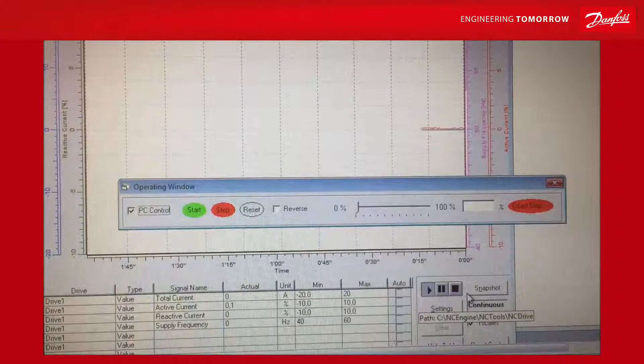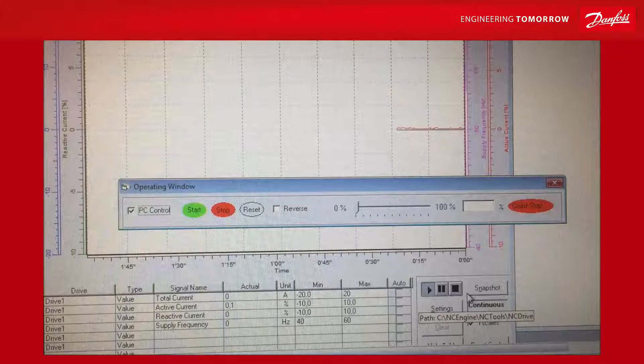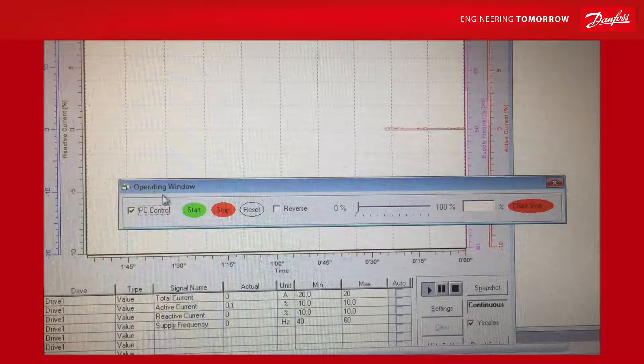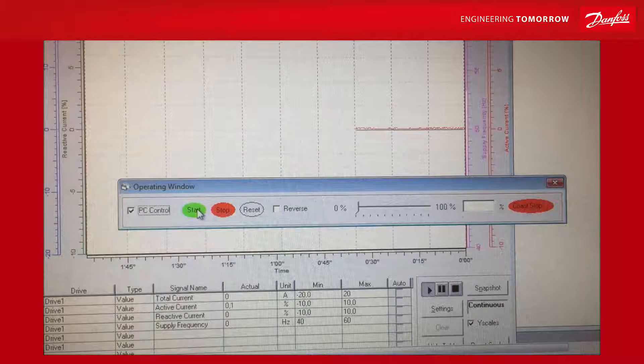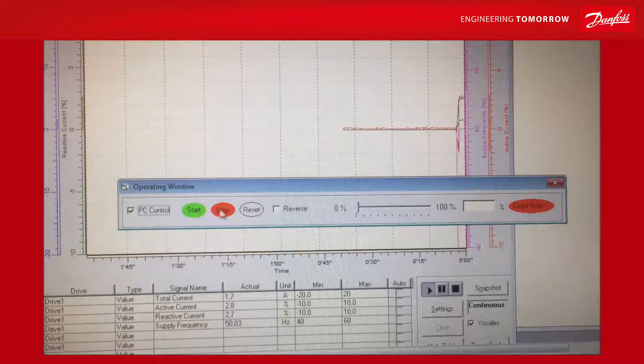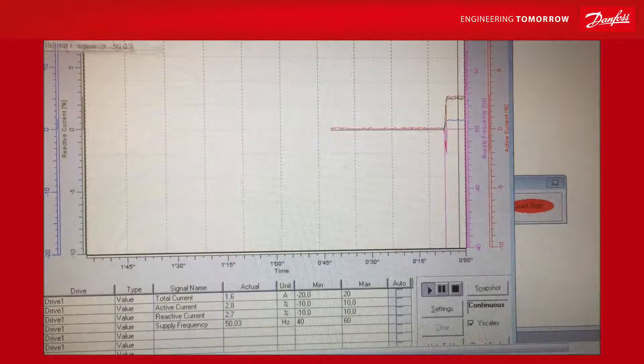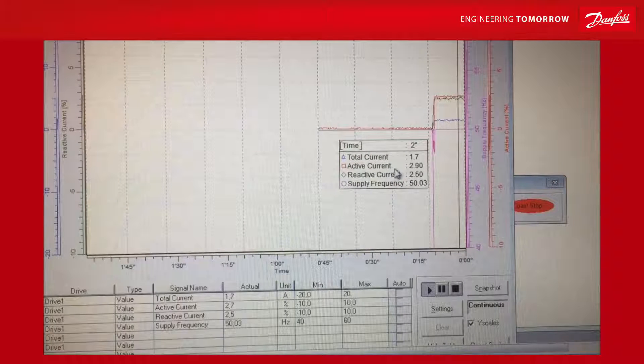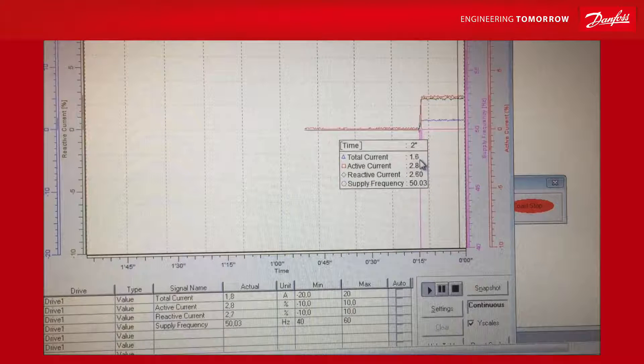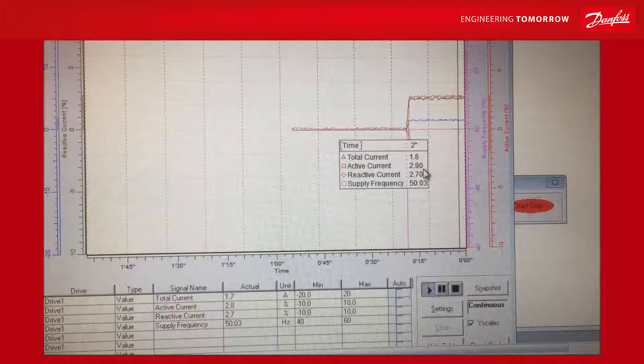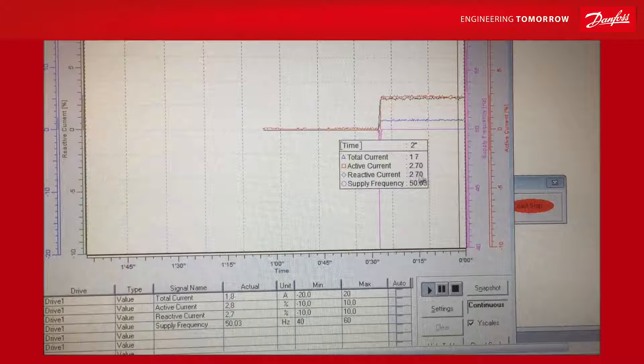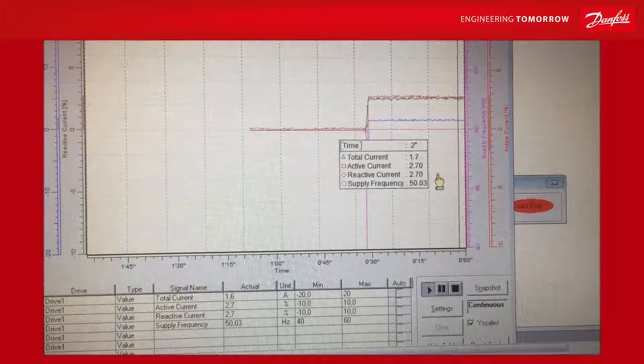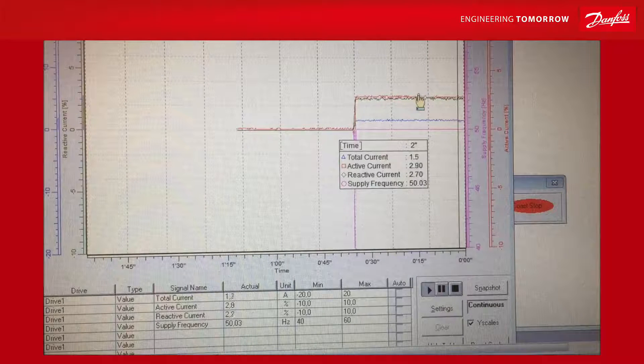With only those few basic parameters in, let's try to start it, just like it was a shore power. It is not synchronizing to any grid yet — it is just making its own grid. We have selected the operating window, PC control, so my laptop is now start/stop of this system. I can reset any faults, hit the start button, and the thing starts. Here I can measure and take a look at values. The current is pretty low — 1.6 ampere total current. The active current is 2.9% of 40 ampere and reactive current is 2.7%, which reflects the consumption and losses in the LCL filter running in open air.